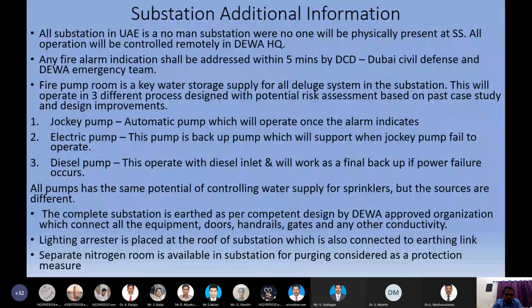The complete substation is earthed as per the design by a DEWA approved organization, which connects all the equipment, doors, handrails, gates, and any other connectivity. Not only the earthing, but the civil phase, electrical phase, mechanical phase, plumbing phase, fire hydrant phase, testing and commissioning phase, in all the phases the contractor should be approved by DEWA, the Dubai Electricity and Water Authority. Without that, they cannot work in DEWA substations, and this will be verified at each stage of the process, and even at the commissioning stage as well.